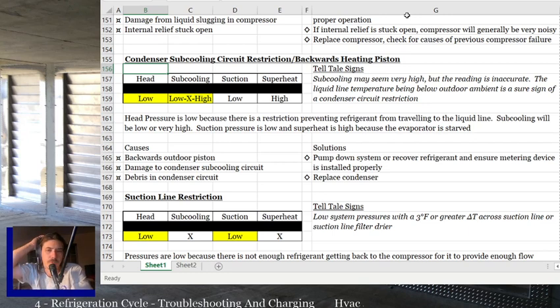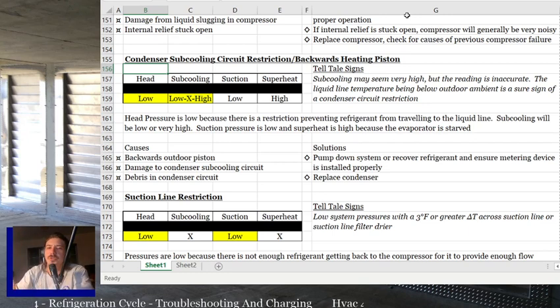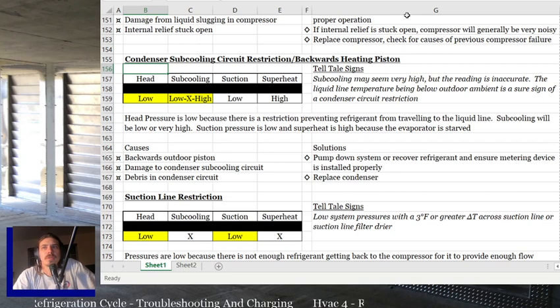Not unless you've got water on the coil. Then let the coil dry up and verify it's still the same. But if it's 80 degrees outside and that liquid line is 70 degrees, something's going on. There's some kind of restriction, because you can't make 80 degree air make refrigerant 70 degrees. It doesn't work like that. Okay? So that's really what you're looking for.